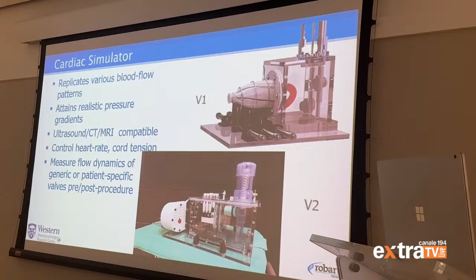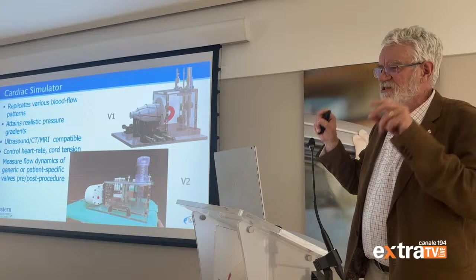This system can very accurately reproduce the dynamics of the heart valves that we would see in a normal patient. It can reproduce the important pressure differentials that we see on one side of the valve and the other side of the valve. We can control the heart rate. We can give it very realistic heart beating patterns. We can measure the flow rate. We can adjust the tension of the cords that are holding the valve leaflets in place. So it's a very elegant way of putting an artificial valve in a very, very controlled environment.